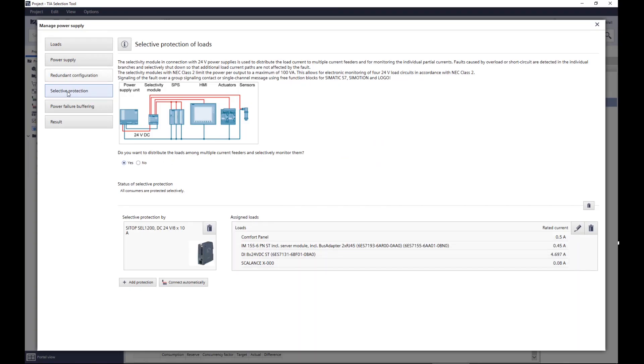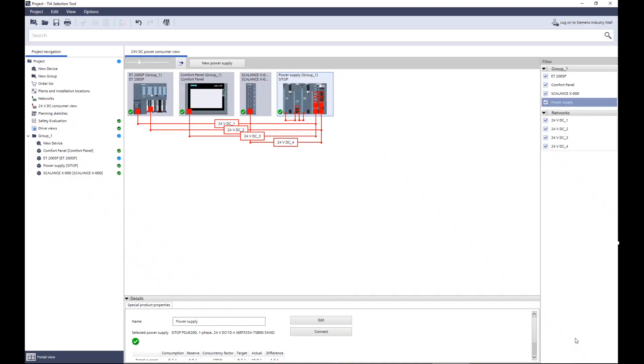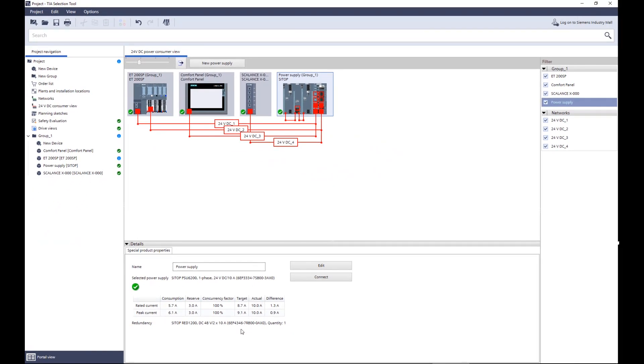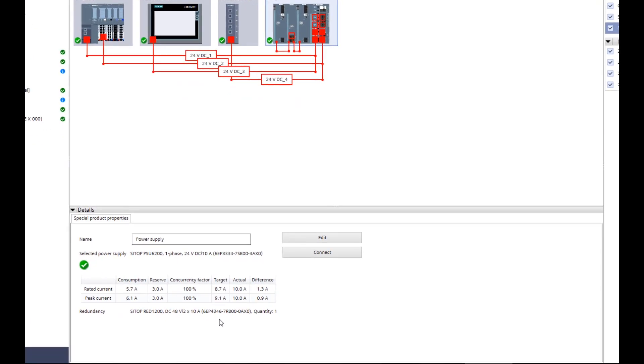The last configurable component for bridging power failures is not required for this project, so the wizard will be led back to the 24V view via the Result and Apply Selection button. Here, the selected power supply PSU 6200 with 10A, the redundancy module RED1200, and the selectivity module SEL1200 are already placed and connected to the loads. Further details on the nominal and peak currents are listed in the lower part of the window.